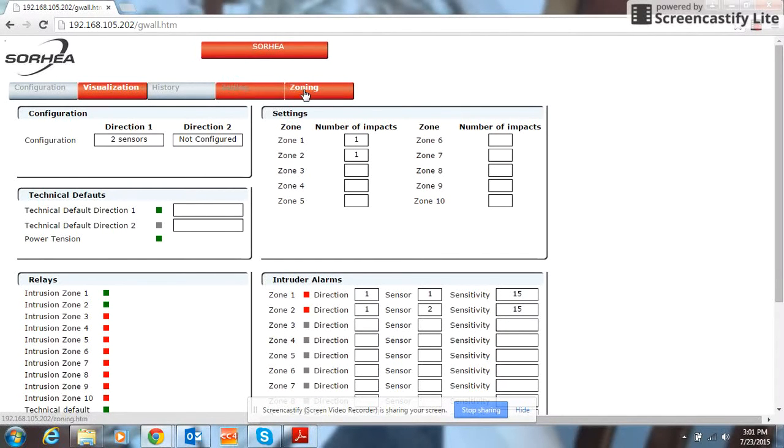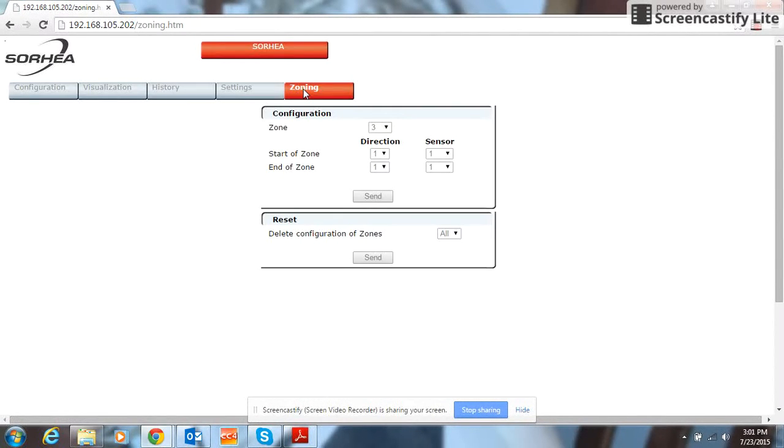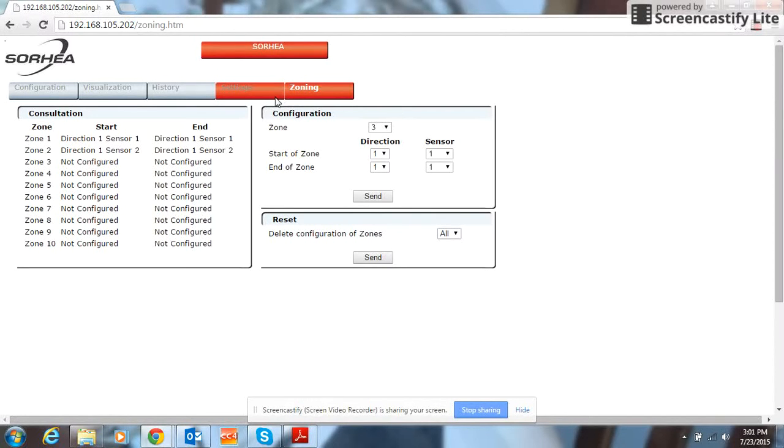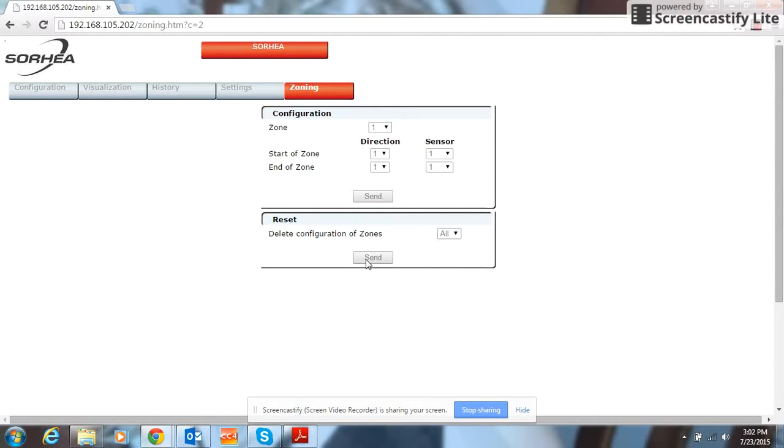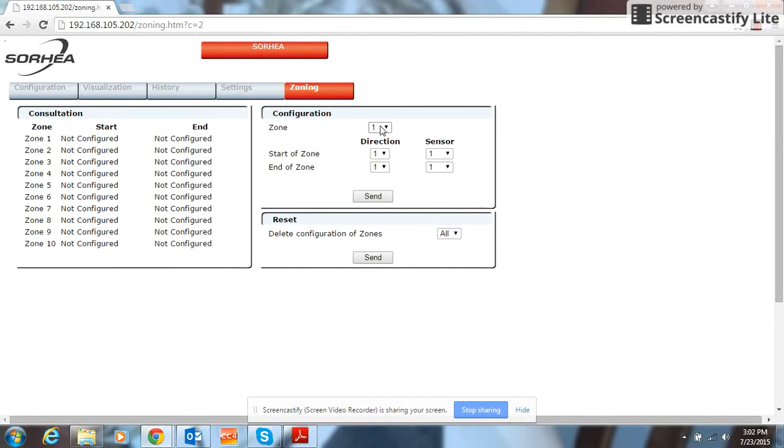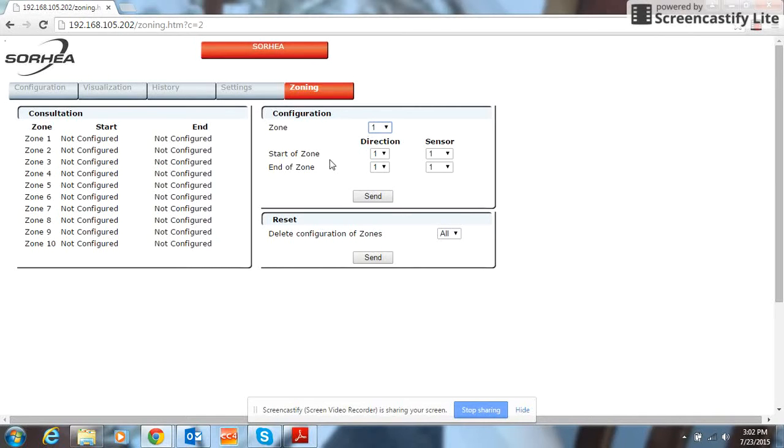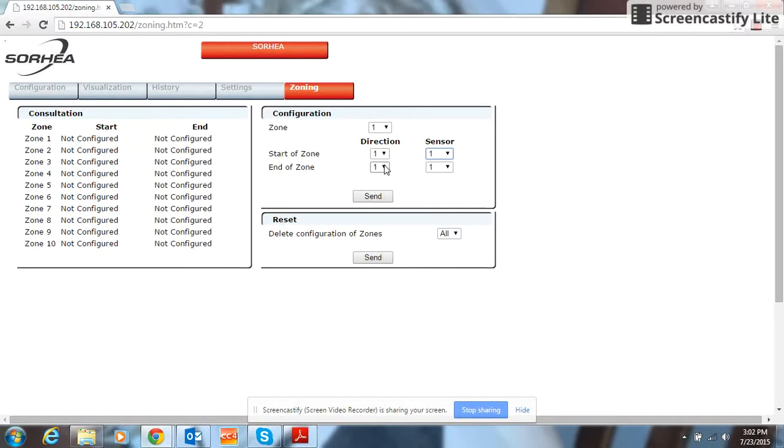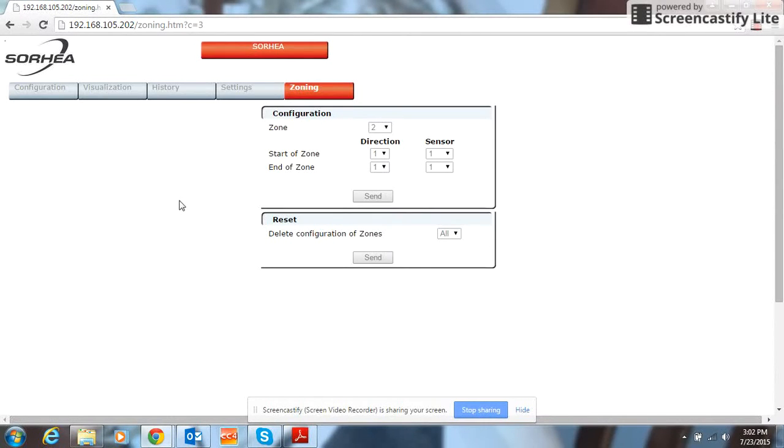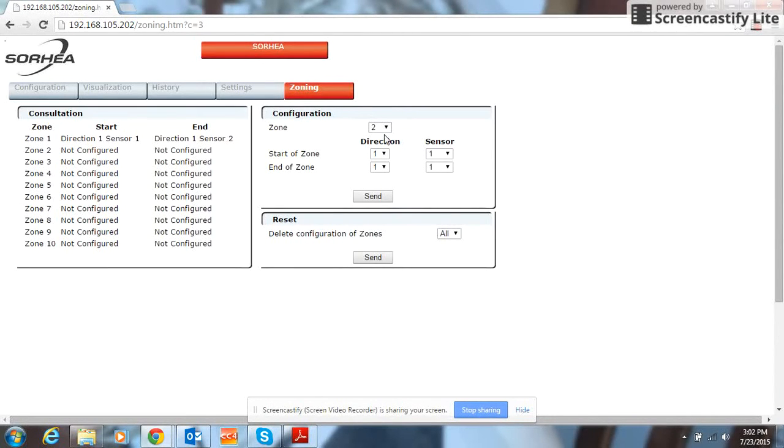So we can go first to zoning, and the first thing you're going to want to do is go over here to delete zones and click send. Now we can start off fresh. Go to zone 1. We want zone 1 to be detection cable direction number 1. We're going to start with sensor 1. Since we only have two sensors on our cable, we're going to end with sensor 2. So now we have one whole zone for our detection cable.